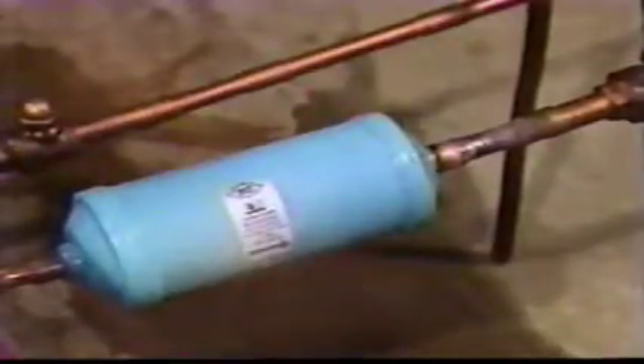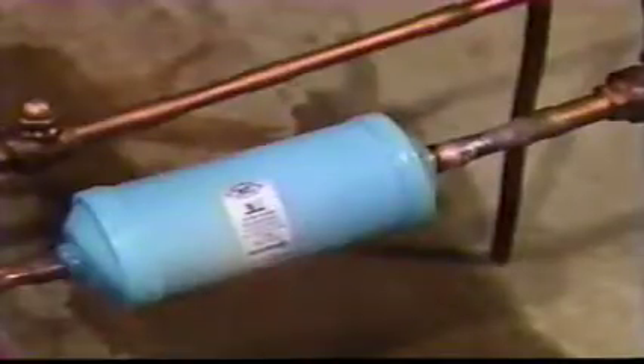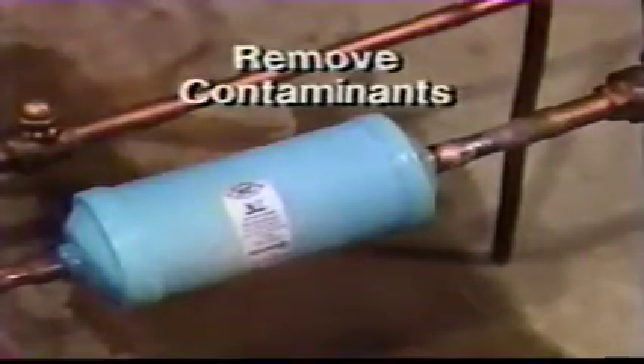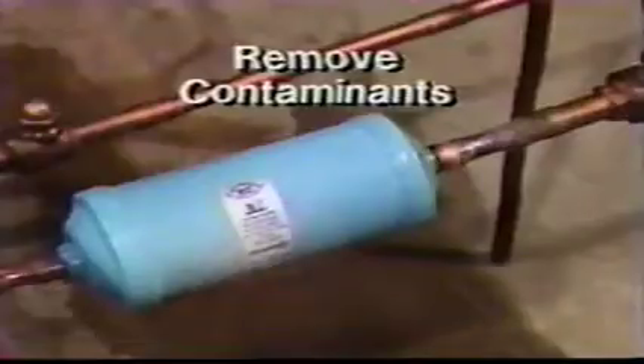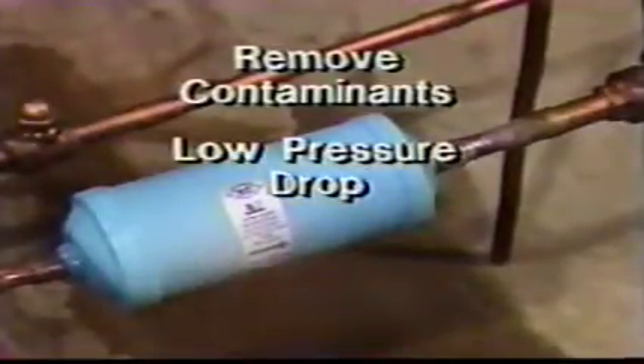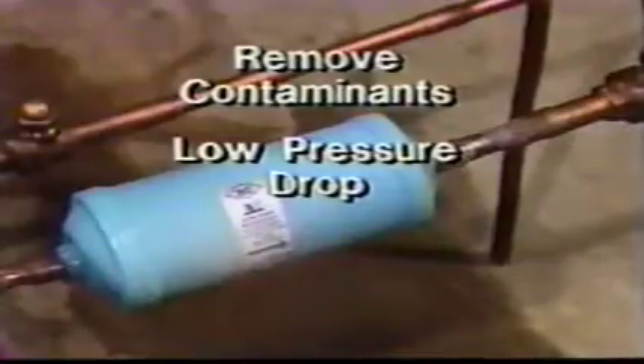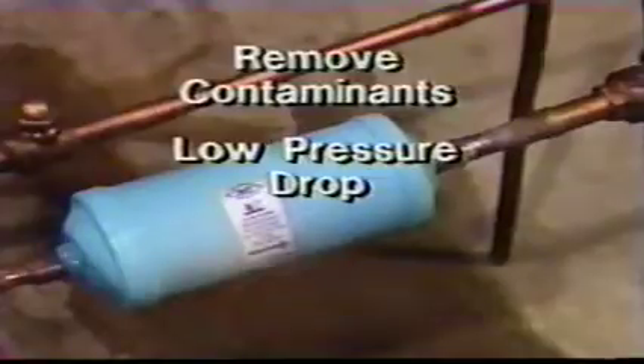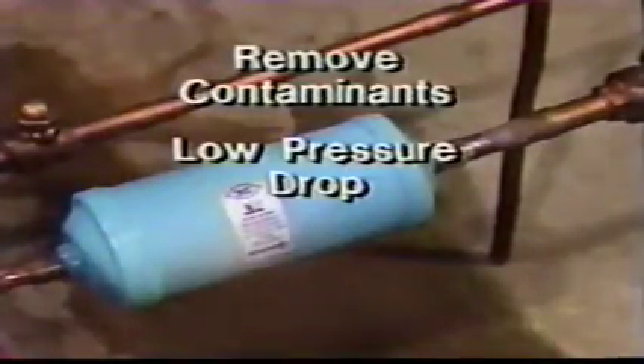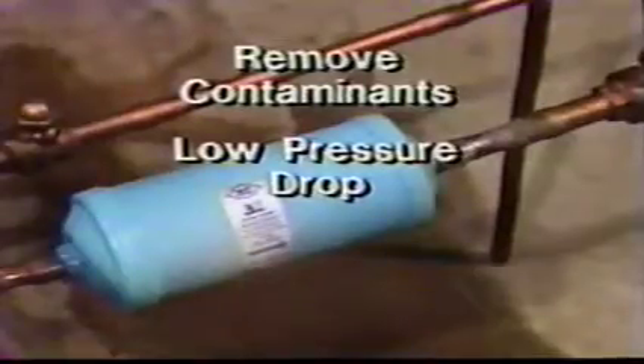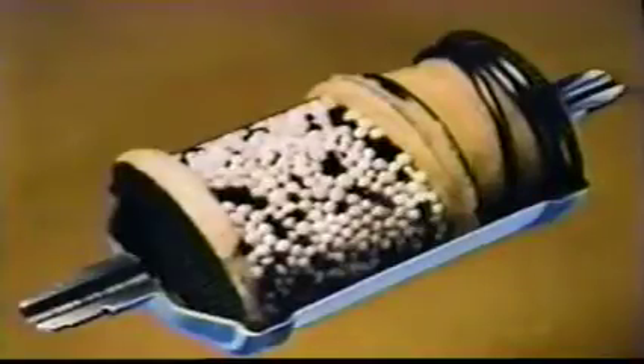Quality filter dryer design provides two important benefits. The filter dryer must be built to remove all contaminants, and the filter dryer must never be a source of excessive pressure drop. The service technician's world would be an easier one if there were one filter dryer to do these two things in all situations. No such filter dryer exists. Like so many other things, filter dryers are specialists at what they do.